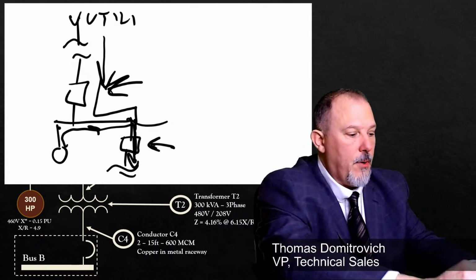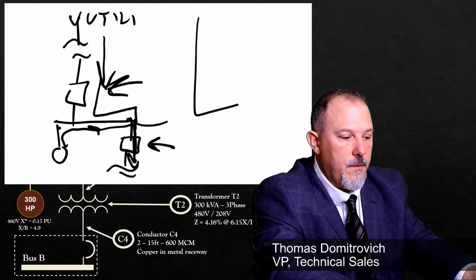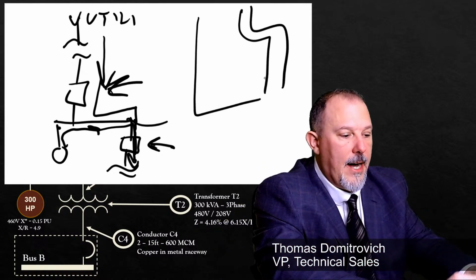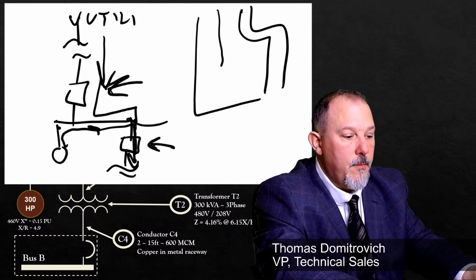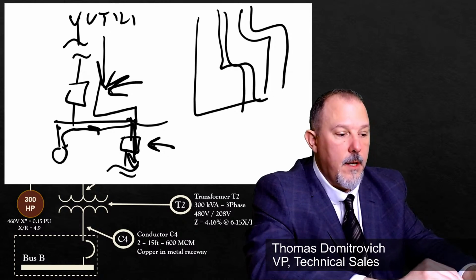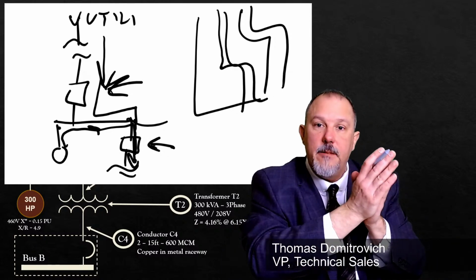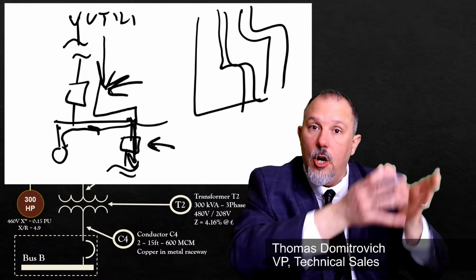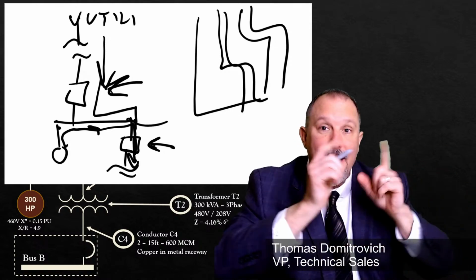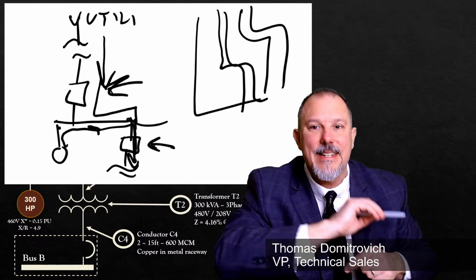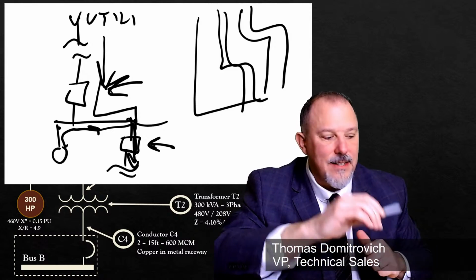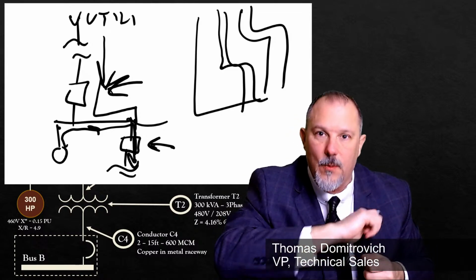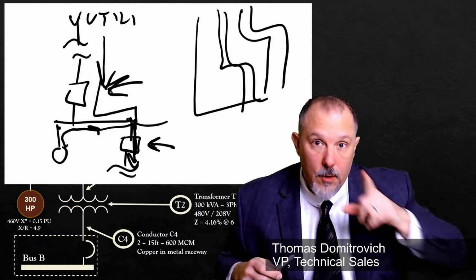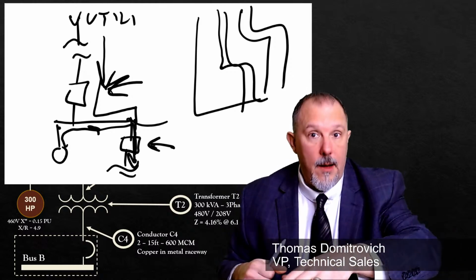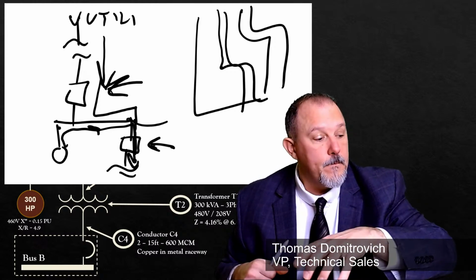So I'm going to plot the upstream breaker's curve. I'm going to plot the downstream breaker's curve. And I'm going to say, I need to make sure that I have separation of curves in the overload region. And if the fault current is high enough that it's in the instantaneous region of both breakers, that's when you've got to jump through some hoops. And we're going to talk about how you solve problems with selective coordination.